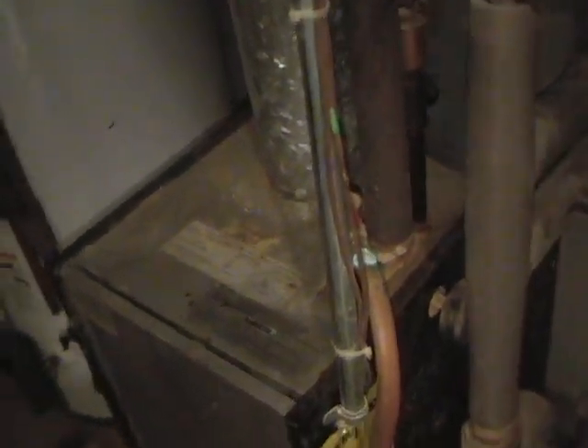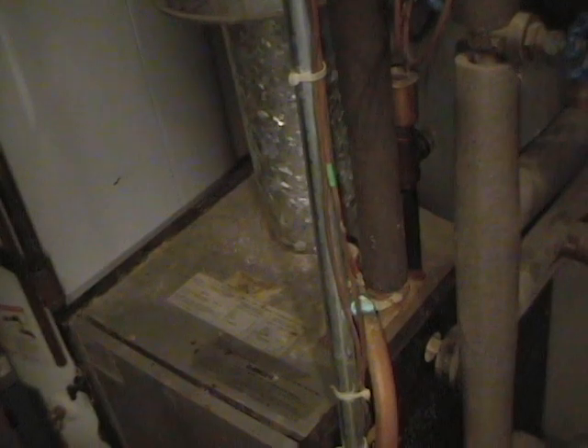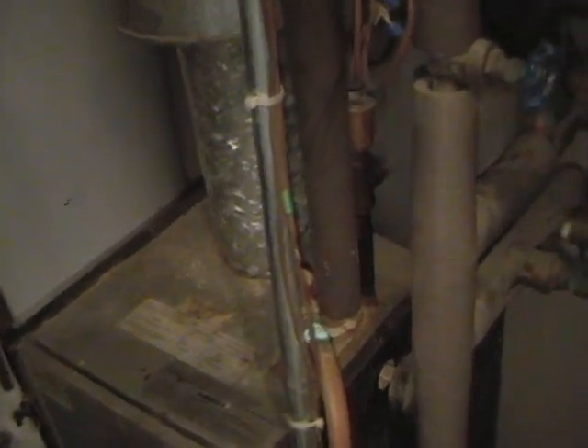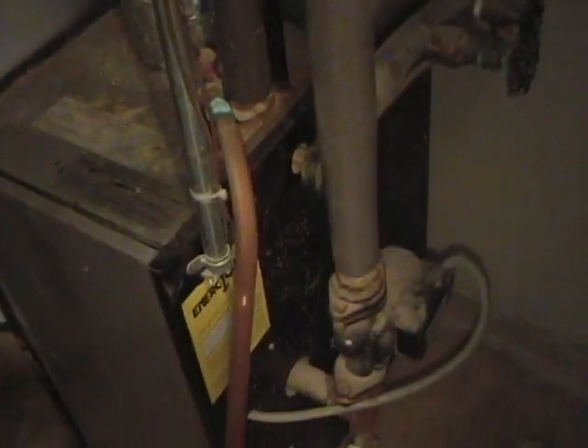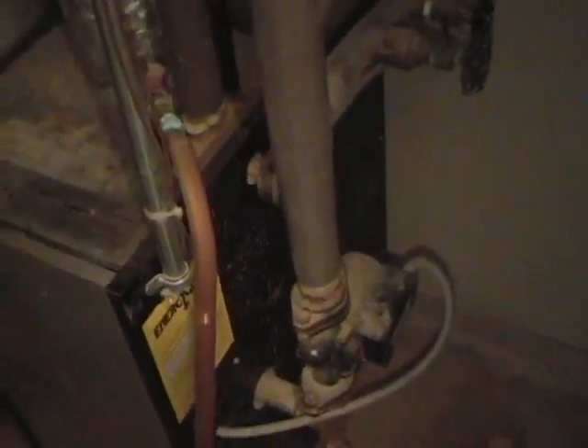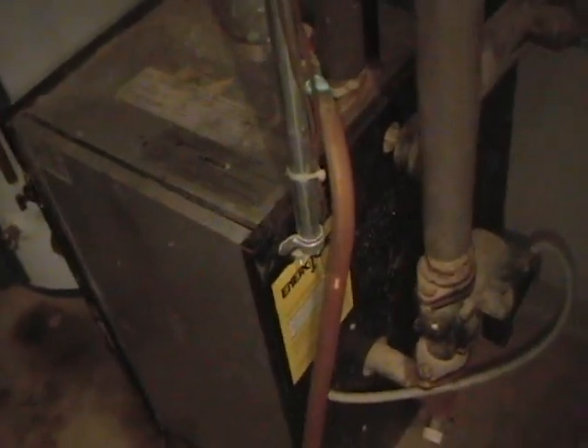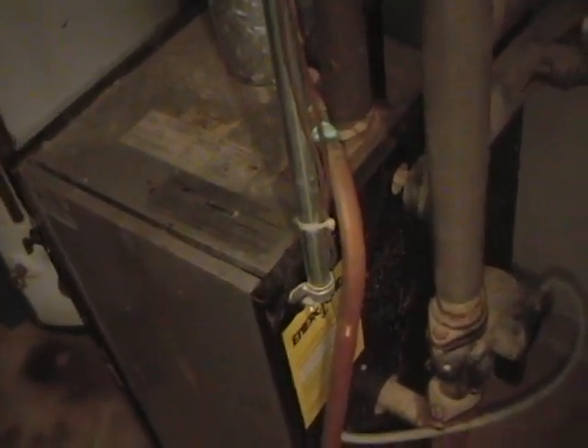And oh yeah, by the way, the water temperature range for the boiler is 160 to about 200 degrees. What I mean by that is, if the boiler is running and the water reaches 200 degrees, the burner will shut off while the pump continues to run, so that it doesn't get too hot, possibly boil the water, and then the pressure gets too high. So that prevents that from happening. And then once the water gets below 160 degrees, it turns back on to keep the water heated for the heat exchanger.